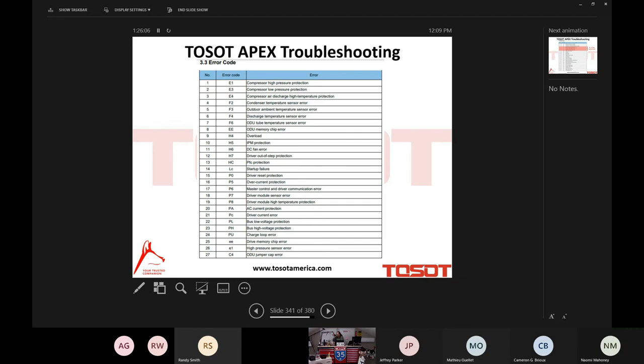E1 is high pressure, whether it's a mini split, Tosot mini split, or an Apex system. So many of the error codes are identical, but not all of them. I point out to you F2, F3, F4, and F6. Those are the thermistors of the outdoor unit. Each thermistor is a beautiful thing, my friends. Each thermistor has its own unique error code.